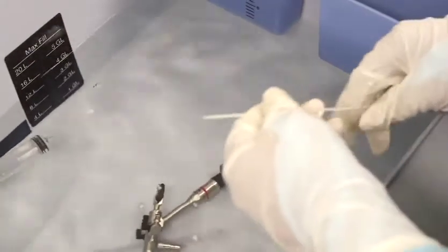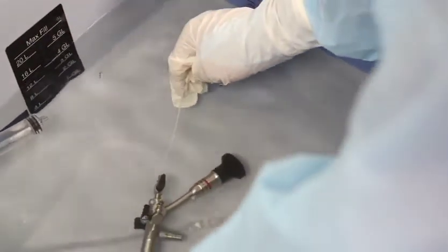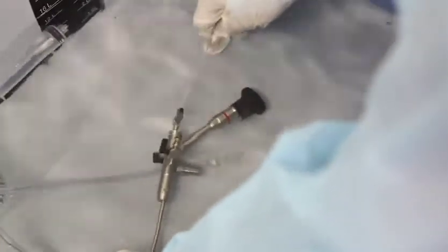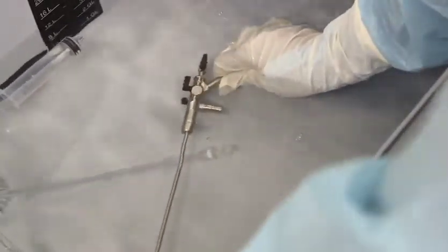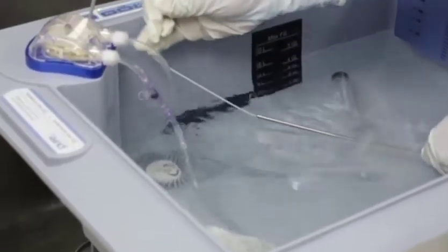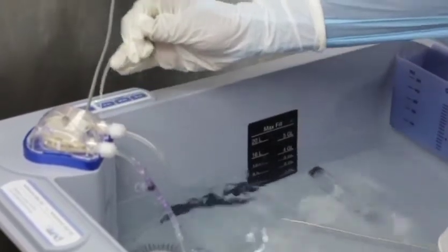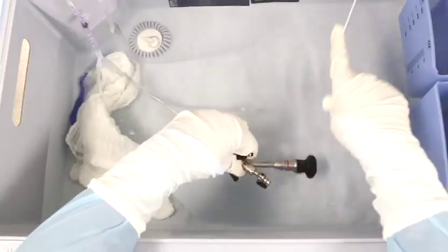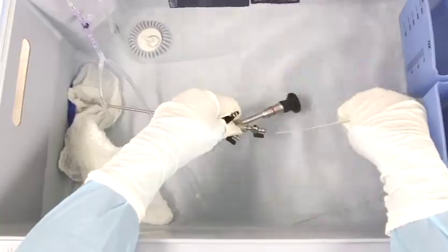Use the correct sized brush to clean the endoscope's channels. The diameter of the endoscope should match the size of the brush bristles. The bristles of the brush should touch the surface of the channel without folding or bending the bristles. Brush the endoscope channels with the endoscope submerged in the enzymatic solution. Make sure the brush moves completely through the channels without kinking or bending the handle.